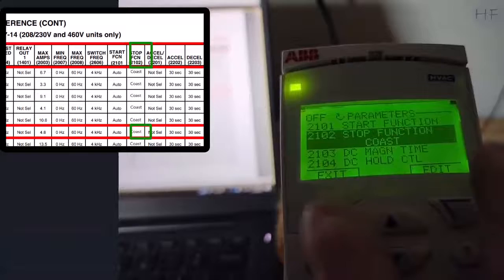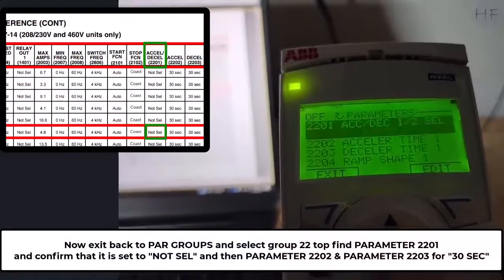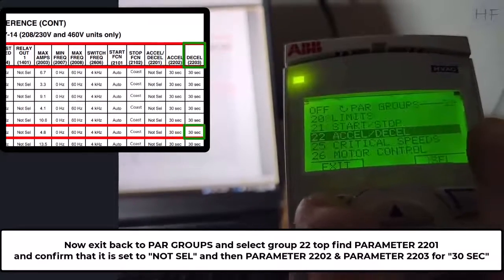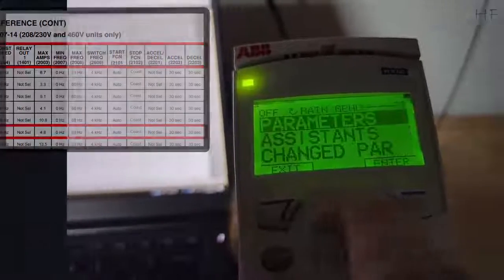Now exit back to parameter groups and find parameter 2201 and confirm that it is set for not selected, then confirm that parameters 2202 and 2203 are set for 30 seconds.